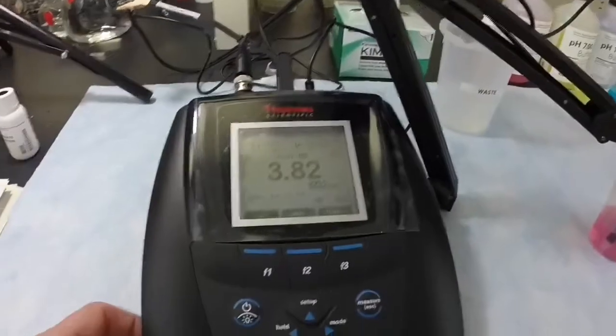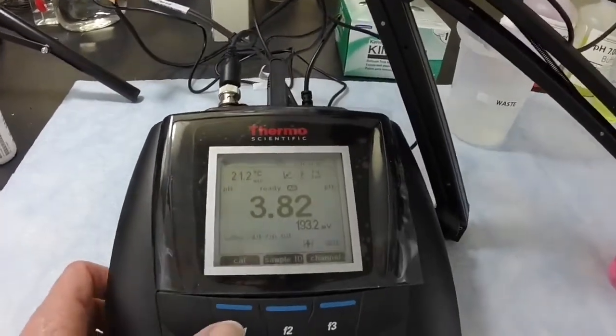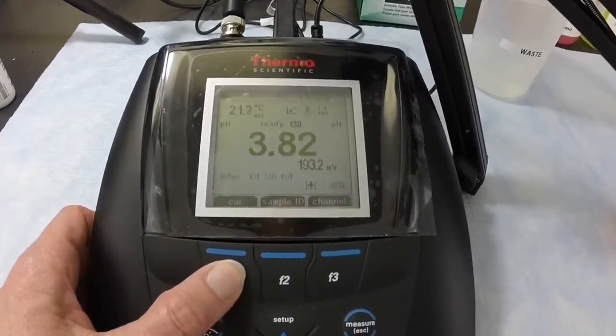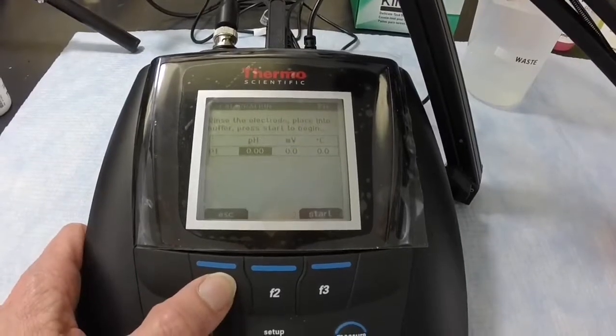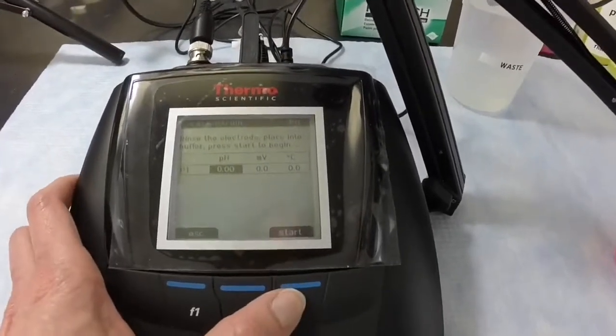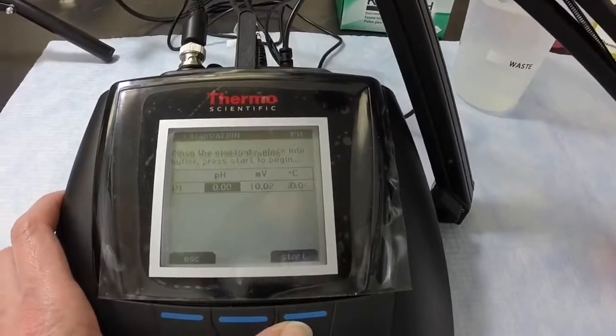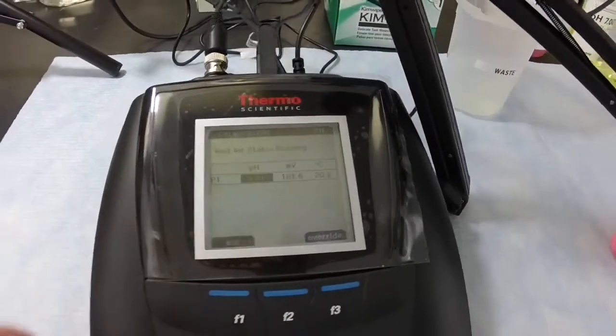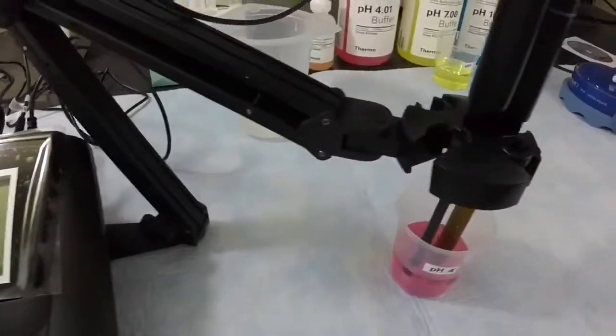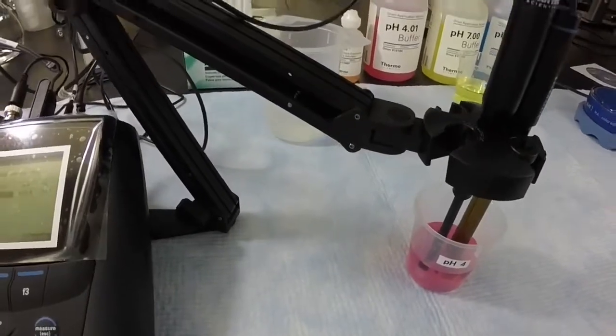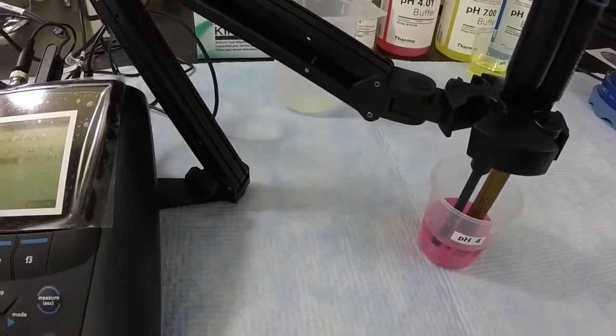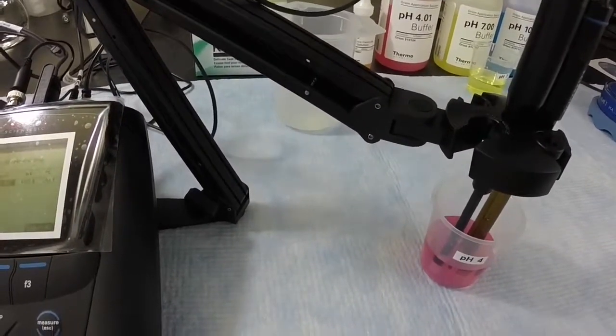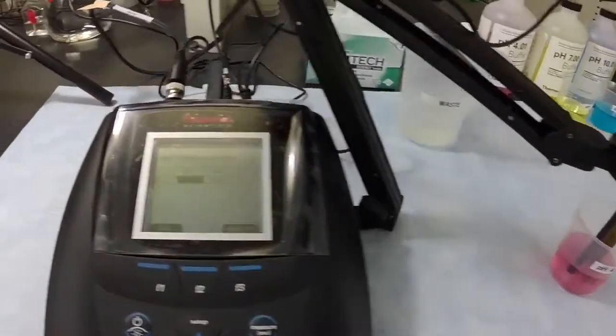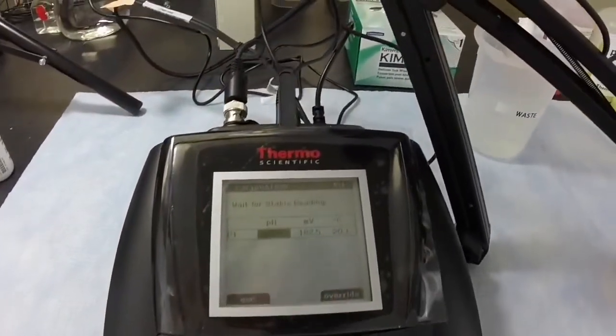Select the cal function on the meter by pressing the F1 key. Then, select Start by pressing the F3 key to begin the calibration. When using the mechanical stirrer, stirring will start automatically. If using a stir bar and a magnetic stirrer, start the stirring manually now. The pH reading will blink on the meter display until a stable reading is reached.